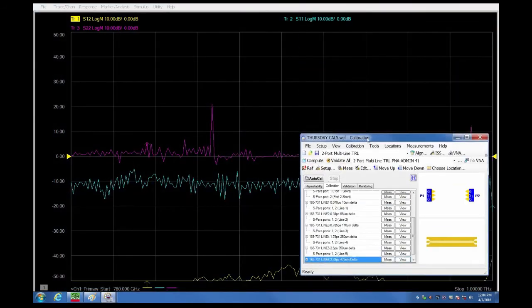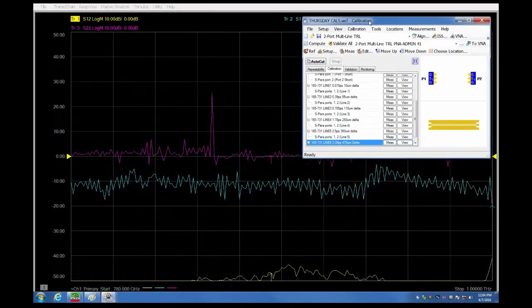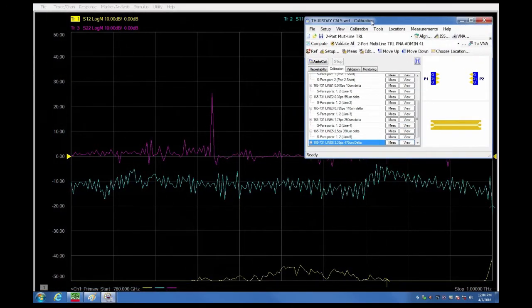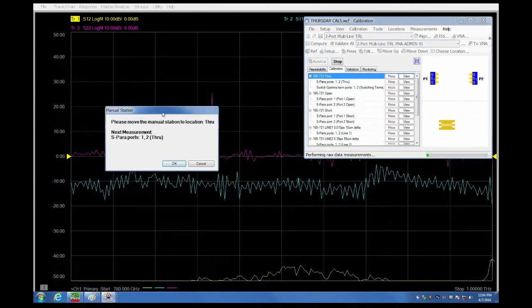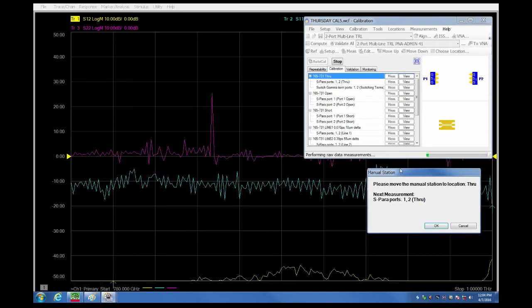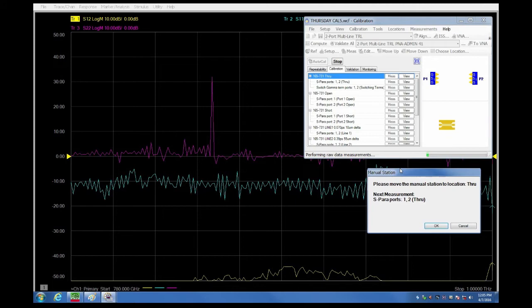We bring up WinCal on the same screen as the PNA software for this video but usually WinCal and PNA software would be on separate screens. We start the AutoCal. During the AutoCal WinCal will prompt us stage by stage for the different standards that it requires until all the data is collected.